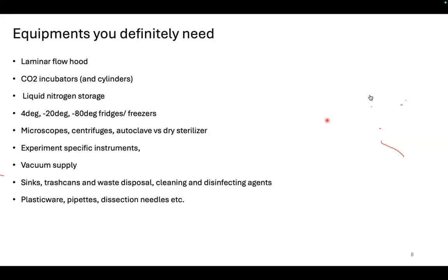The only thing is, and again we'll talk about this in more detail, whenever you're going to finally use it, you need to be sure that it's clean from outside. So you just spray some ethanol on it, wipe it off with a tissue, and then use it. Because when you're working with water, let's say there was a water droplet on that tube, you don't want that to contaminate what's inside. So water bath is perfectly good to use, but just be careful and keep changing the water. Anyway, it's going to evaporate after some time.